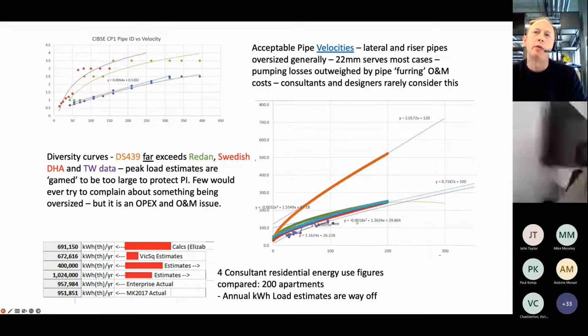I've thrown up a couple of other ones on there, Redan, the Swedish District Heat Association, and our own data. And it suggests that the peak loads are being far too overestimated by people. And yet that's due to the fact that there's an imbalance in this equation. A lot of people will be oversizing because nobody's forcing them to undersize, because a lot of the oversizing faults occur in the O&M sphere.